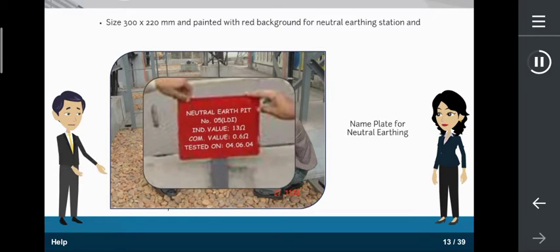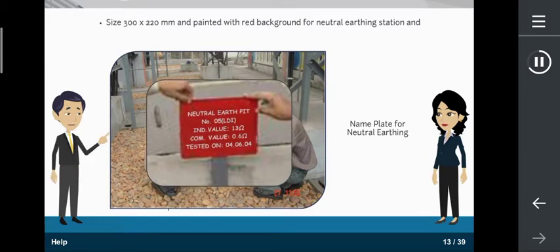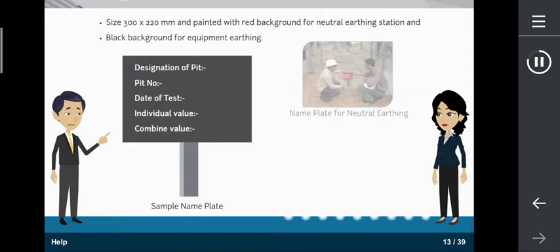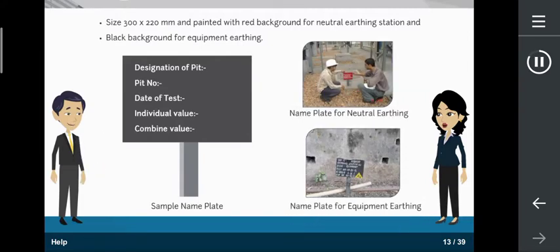These identification plates have the following dimensions. For neutral earthing, the size should be 300 by 220 mm and painted with a red background for the neutral earthing station and a black background for equipment earthing. Now I get it. That really helped. Thanks, Mayank. Anytime.